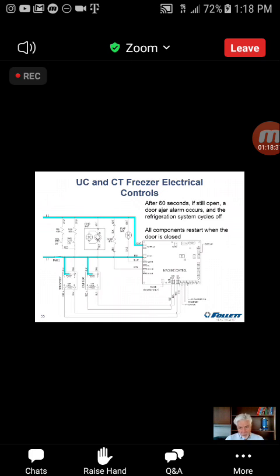The moment it's closed, we go back to normal running, but that door ajar alarm has to be acknowledged. That's not going to go away. The visual alarm will stay there. So that's it for the operation. Now the DFA alert. Remember, on a refrigerator, it's almost always an issue of the way the product is loaded into the refrigerator. It can be other things, but it's very, very seldom, very rare. On a freezer, this is a different story.